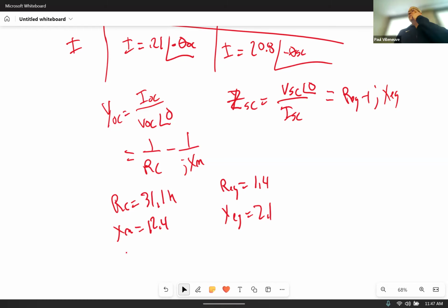Yes, sir. Question about the 50 kVA. You don't use that at all. You do use it. The 50 kVA was when you calculate the short circuit current. Okay. But did you need it for any of these calculations? No, that's just to actually do the test. Just like if anybody did the transformer bonus for the exam, it's the same thing there. We needed to know what the impedances were. So we needed the 68 MVA or the 80 MVA, whatever you use, we needed those data points. So you need it for the baseline data, but it actually isn't part of the test.